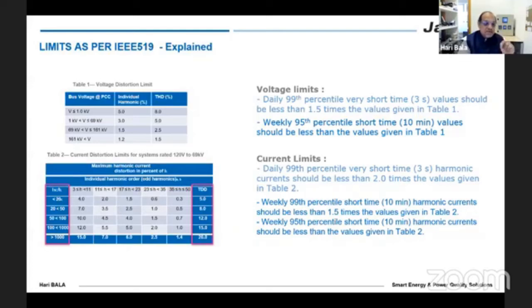Whereas a similar customer who has an ISC by IL value between 50 to 100 can have a higher level of harmonic. Say the third harmonic can be up to 10% as per the table. So it has to be clearly understood what level it has to be. Same way for the total demand distortion as well. The lowest allowed is 5, and the highest allowed is up to 20, depending on the ISC by IL value, which means calculating the ISC by IL value for all the consumers plays a crucial role in determining their TDD values and the harmonic limits.